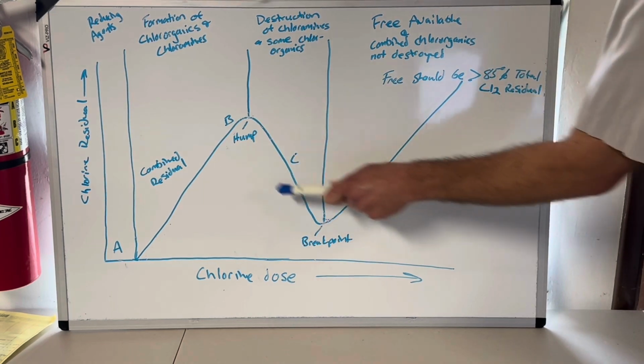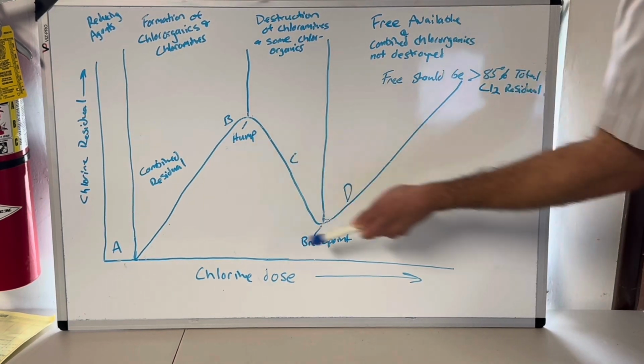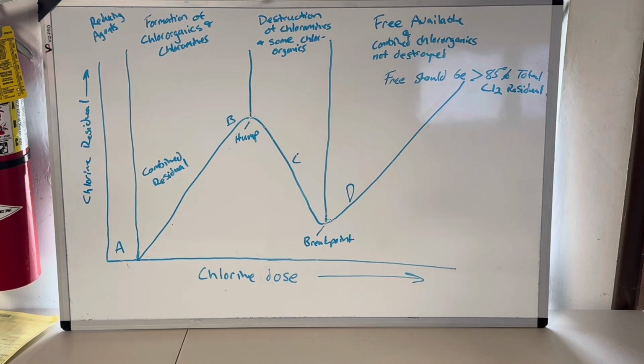There was a 1 over here. I want to run at least a 6. If I'm under a 6, I change the ratios. I mess with this a little bit and tweak my chlorine. I start running free ammonia samples to see how much runway I have.